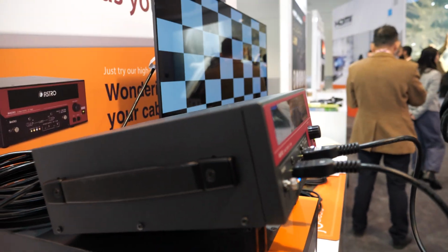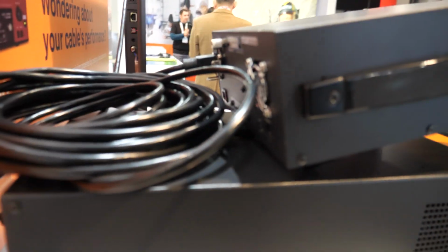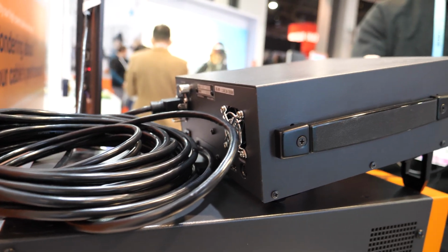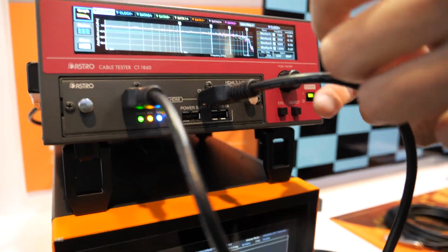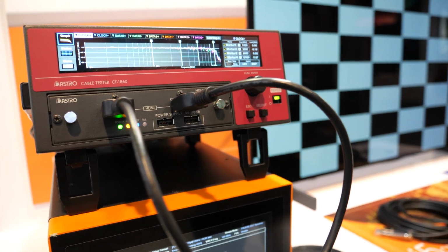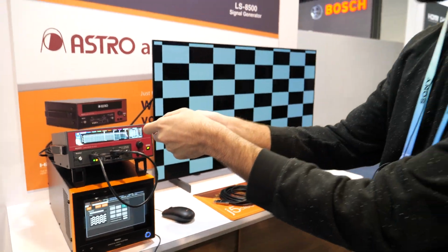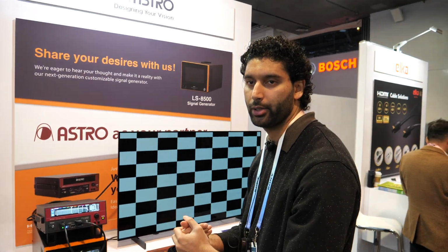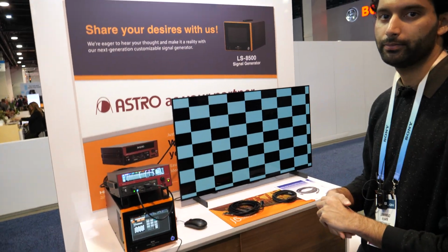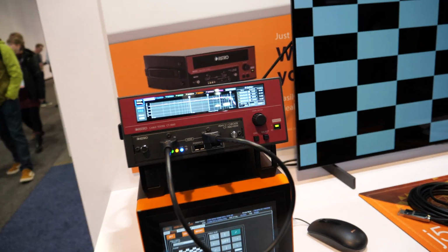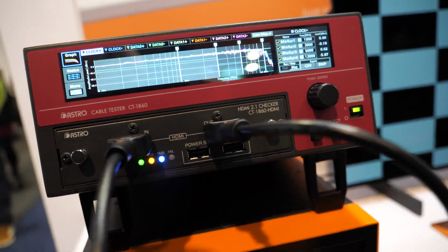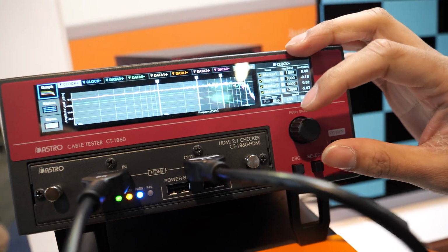So once I set up my parameters, let's say if I want to test a series of cables, I can just simply take this off and plug in a cable, and it'll let me know whether it passes or fails. Nice. There's no need to set up anything, it's just ready to test. It's ready to test. All you would have to do is set up your parameters, and then you go from there. Push to enter, you can scroll in the menus and stuff.